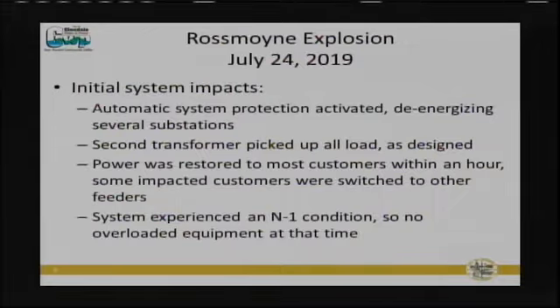And then we proceeded with working on what we were going to do to repair the transformer, because it was one of two transformers at the station that was impacted. We have 13 stations. And of the 13 stations, this particular station provides power to four total stations. Of those 13 stations, there's 116 circuits, and there were 32 circuits involved in here, and approximately 25% of our customer base was impacted by this. So the other substations that were impacted were Scholl, Fremont, Howard, and Rossmoyne itself.